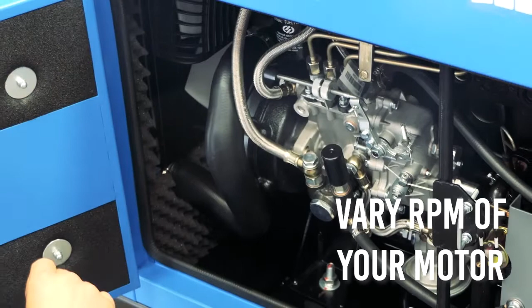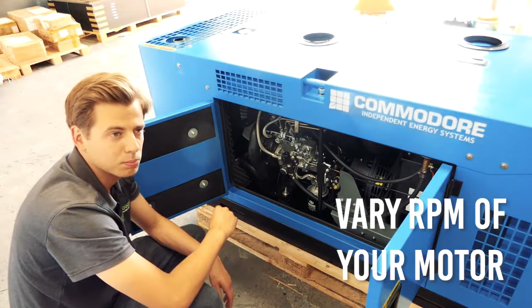So if you need to, this is the adjustments for your frequency. These two tabs here. So you unwind that and just move it backwards and forwards. And that'll vary your RPM of your motor slightly, and then you just check that back there on the screen to make sure you're at your perfect 50 Hertz.